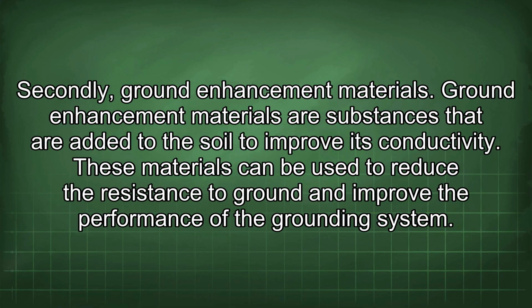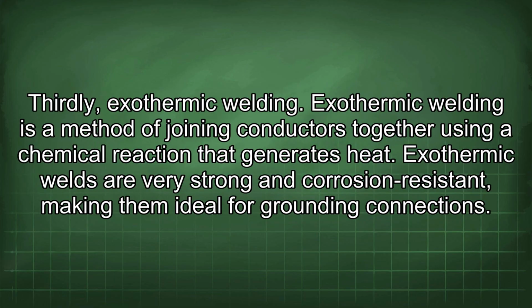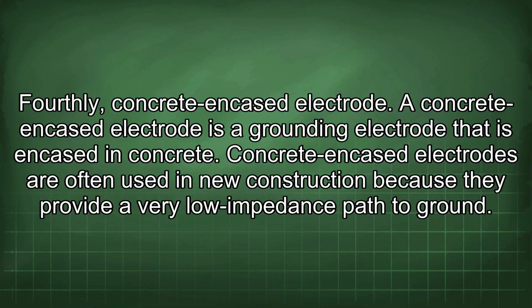Secondly, ground enhancement materials. Ground enhancement materials are substances that are added to the soil to improve its conductivity. These materials can be used to reduce the resistance to ground and improve the performance of the grounding system. Thirdly, exothermic welding. Exothermic welding is a method of joining conductors together using a chemical reaction that generates heat. Exothermic welds are very strong and corrosion resistant, making them ideal for grounding connections. Fourthly, concrete encased electrode. A concrete encased electrode is a grounding electrode that is encased in concrete. Concrete encased electrodes are often used in new construction because they provide a very low impedance path to ground.